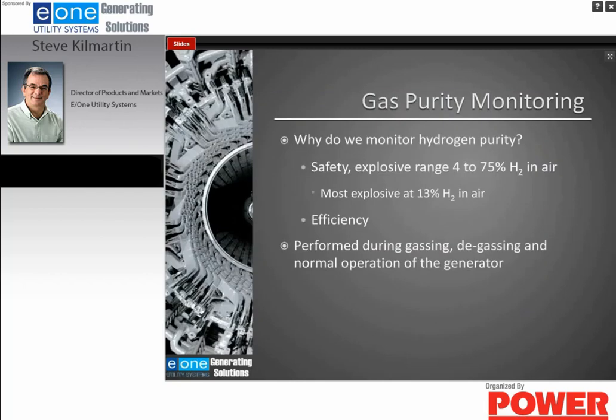Why do we want to monitor hydrogen purity? There are two reasons. Safety is one reason. Hydrogen is an explosive gas when mixed with air, and the range is from 4% to 75%, and it's most explosive at about 13%. So you want to keep the hydrogen pure. You want to keep it above that 75% range.